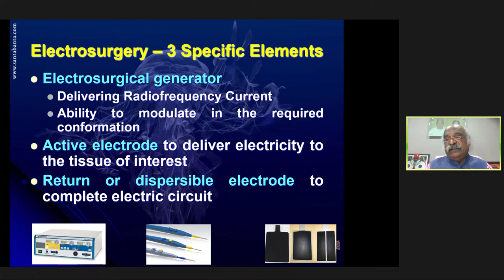So the current flows from the generator to the tissues, through the body, and returns to the dispersible electrode. The current enters at the active electrode and leaves the body through the dispersible electrode to the generator itself, so that the circuit is complete. So whatever the format, unipolar or bipolar, the circuit must be completed. The energy goes through once and returns to the same source. The circuit must be completed.